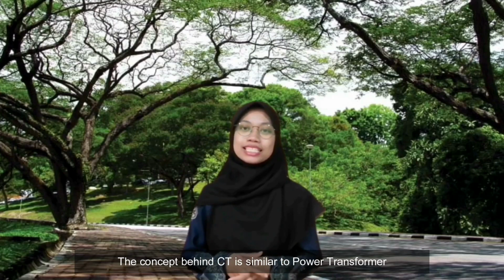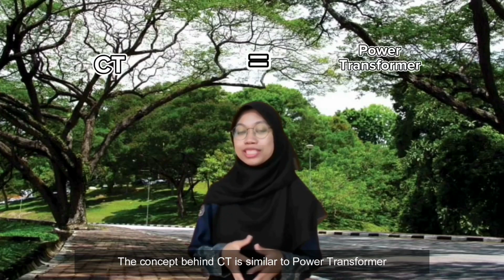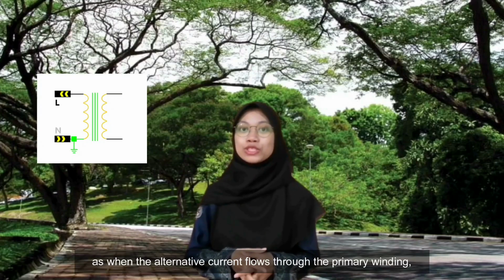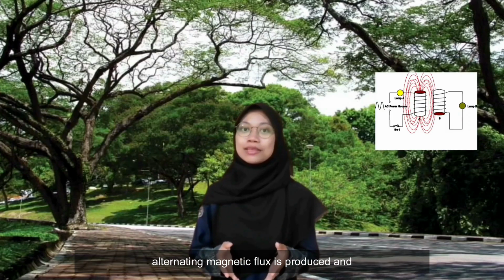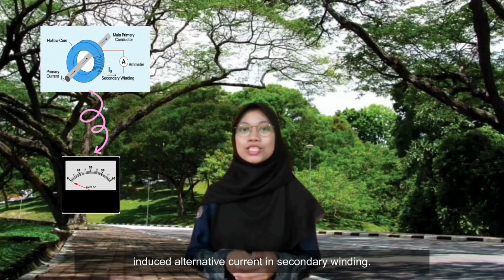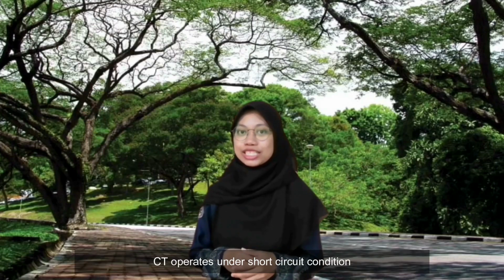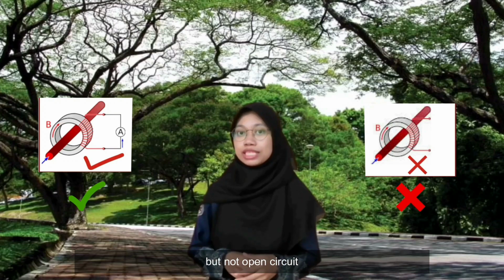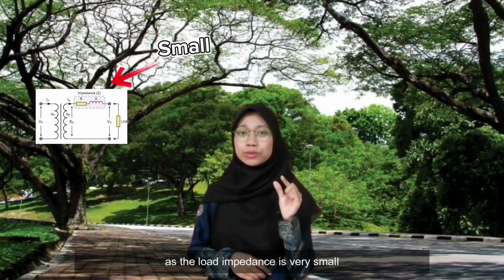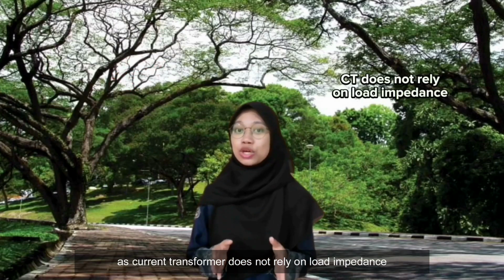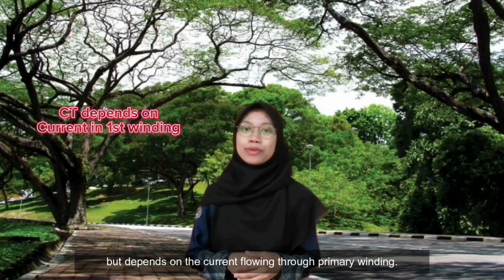The concept behind CT is similar to a power transformer, as when the alternating current flows through the primary winding, alternating magnetic flux is produced and induces alternating current in the secondary winding. CT operates under short circuit condition but not open circuit, as the load impedance is very small, as the current transformer does not rely on load impedance but depends on the current flowing through the primary winding.